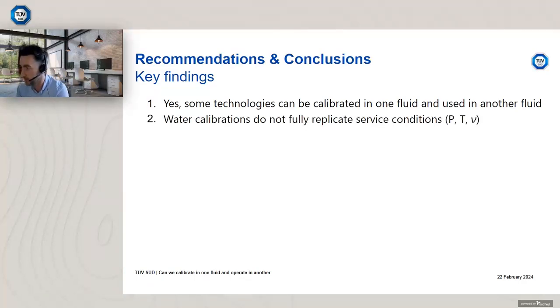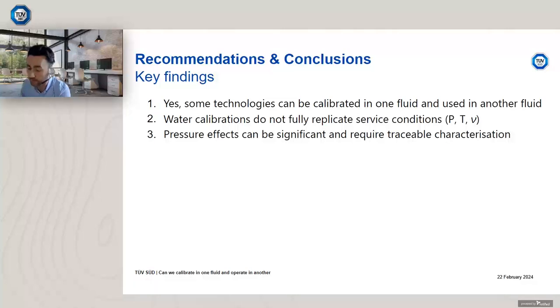It's also critical to bear in mind that water calibrations do not fully replicate service conditions, so you will have an increased uncertainty. Things such as pressure, temperature, viscosity, Reynolds number effects are all potentially going to influence the performance and as such increase your measurement uncertainty. So one key question is, what is your target uncertainty? That's something that we always want to find out first before we make our recommendation.